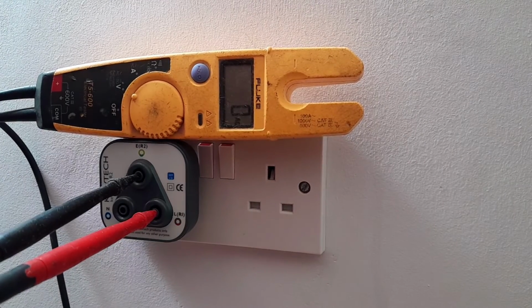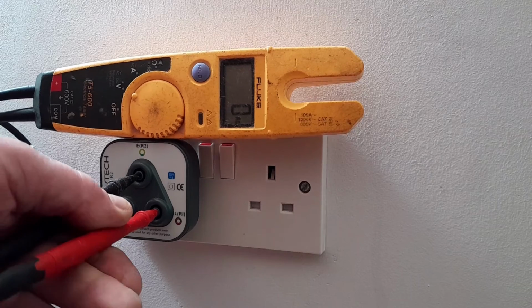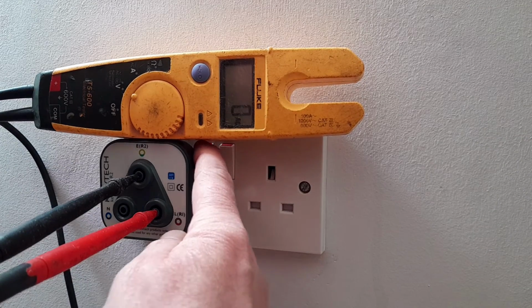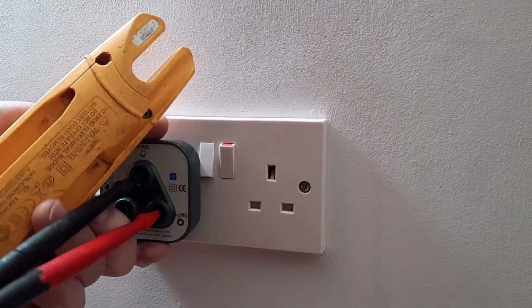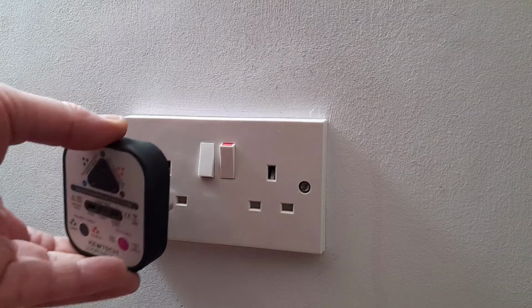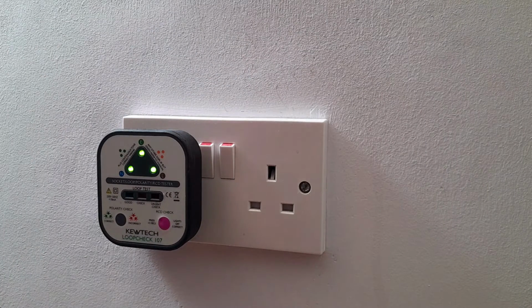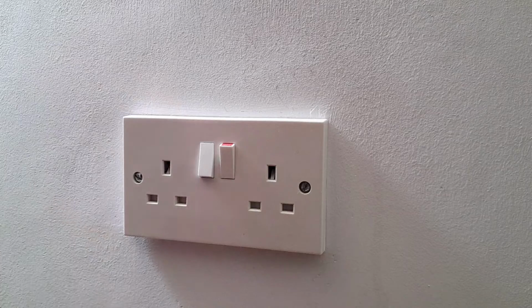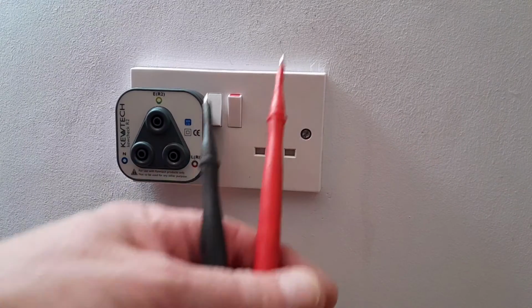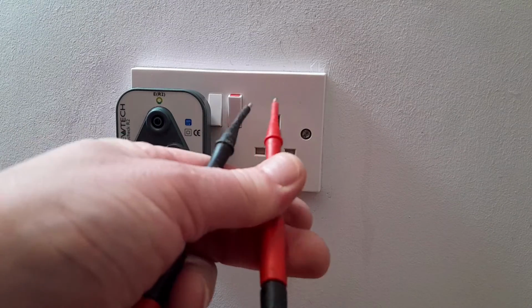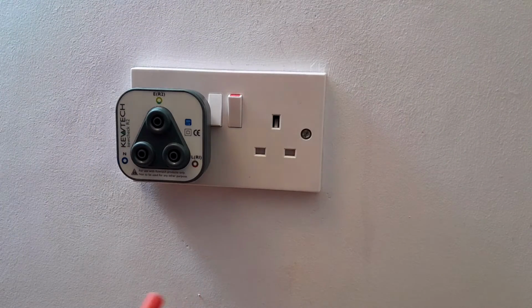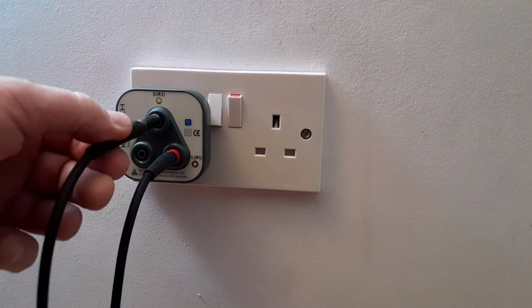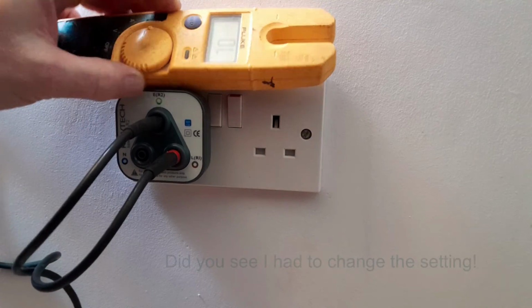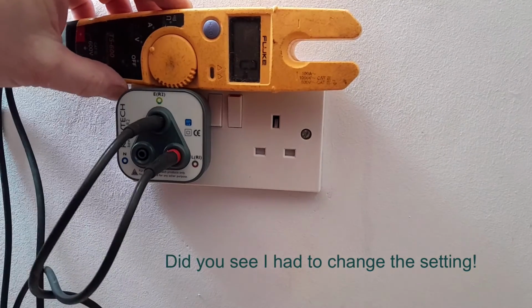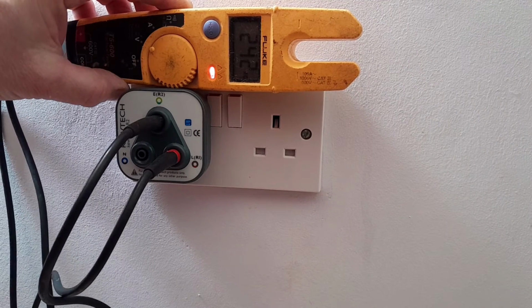Here you can see the voltage tester and the adapter being used incorrectly. Those probes aren't making contact inside, so it's possible that you get a false negative. You think you're isolated when you're not. As you can see when I plug this basic socket tester in, the circuit is energized. If you did want to test this socket, using the socket adapter is the best way to do so, because you don't have to take the socket plate off the wall or the connection is shrouded. The correct way to do it is remove the tips from the voltage tester, if your tester allows you to do so, and you put the leads into the adapter, and you've got a good safe connection. It's not possible to touch any live parts.